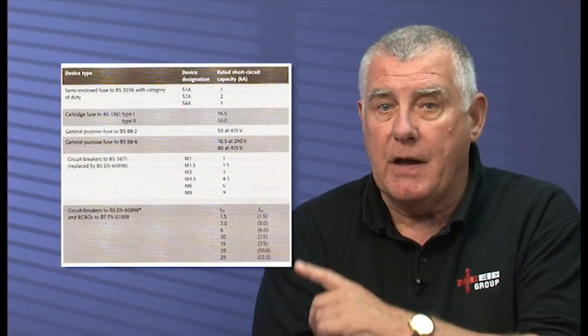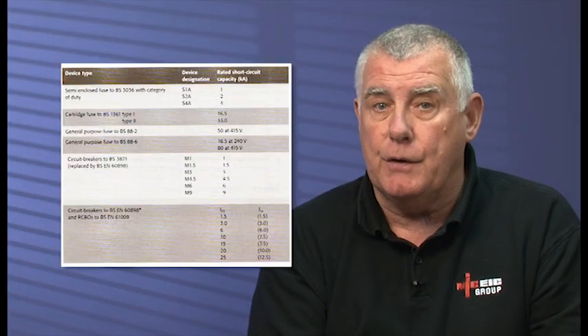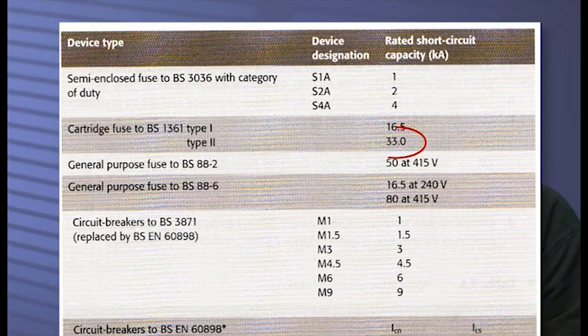Short circuit capacity, on the other hand, is the maximum fault current the device can interrupt safely. Looking back at the data, we can see that a BS 1361 Type 2 fuse has a rated short circuit capacity of 33 kA. And it's this value which must be higher than the prospective fault current we spoke about earlier. There's a good point of warning here. On a periodic, if you did encounter a BS 3036 rewirable fuse as the primary supply overcurrent device, this could have a rated short circuit capacity as low as 1000 amps, depending on its designation.